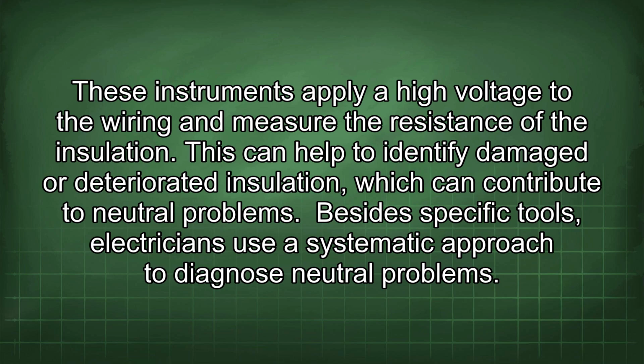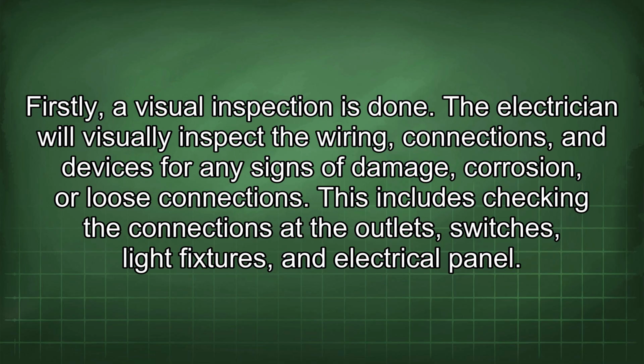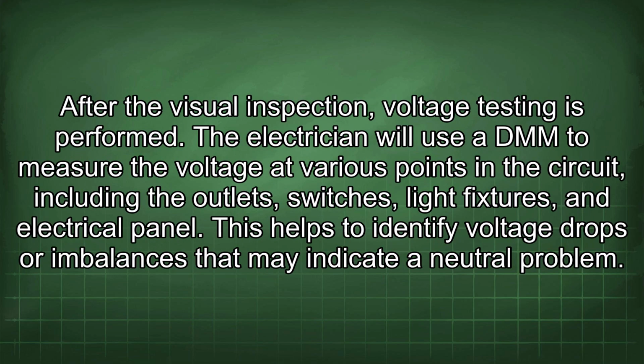Besides specific tools, electricians use a systematic approach to diagnose neutral problems. Firstly, a visual inspection is done. The electrician will visually inspect the wiring, connections, and devices for any signs of damage, corrosion, or loose connections. This includes checking the connections at the outlets, switches, light fixtures, and electrical panel. After the visual inspection, voltage testing is performed. The electrician will use a DMM to measure the voltage at various points in the circuit, including the outlets, switches, light fixtures, and electrical panel. This helps to identify voltage drops or imbalances that may indicate a neutral problem.